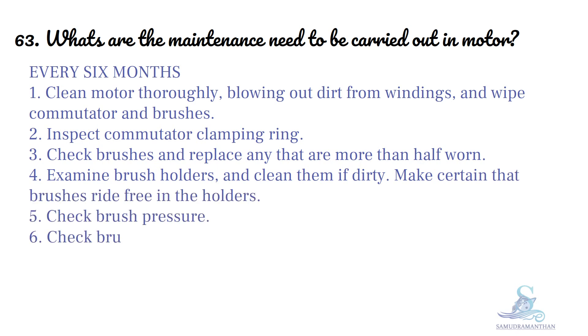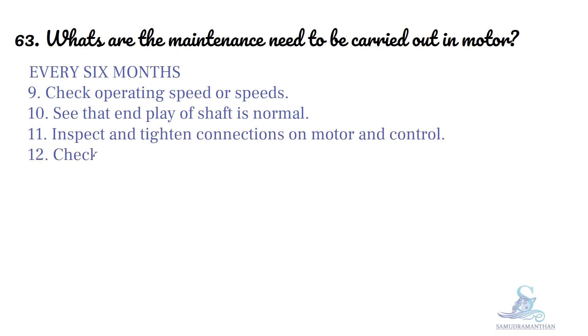Make certain that brushes ride free in the holders, check brush pressure, check brush position, drain, wash out and replace oil in sleeve bearings, check grease in ball or roller bearings, check operating speed or speeds, see that end play of shaft is normal, and inspect and tighten connections on motor and control, checking current input and comparing it with normal.